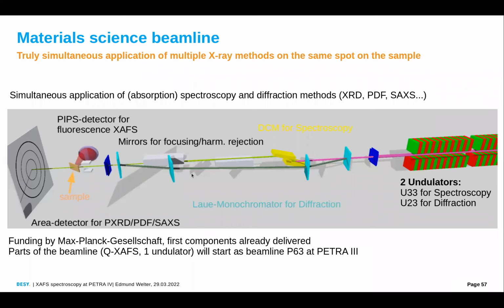So you mean the area detector for diffraction does not see the X-rays for spectroscopy, right? It arrives there, but modern detectors like the EIGER2 allow you to set a window. Oh, I got it. So this way, we would get the ring from the 10 keV, but with the energy discrimination set at 60 keV, we ignore the 10 keV photons. Okay, I got it. Thank you. That's at least our plan.